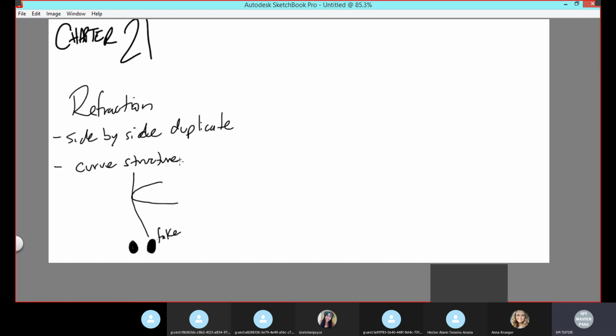And I know things can start getting a little bit confusing, but with practice you'll get it, because I'm just giving you a few words, and these little key words will definitely make a difference. You'll be able to spot the difference by just knowing these little key words. Okay, so that's refraction. Anything that bends, because the book tells you that refraction artifact degrades lateral resolution. So do side lobe artifacts. So anything that starts messing with side by side is going to be bad for your lateral resolution, because lateral resolution is supposed to be the accuracy of things that are side by side. So if all of a sudden you're creating duplicates that are side by side, then that's messing up my side-by-side resolution. All right, that's just one little detail there.